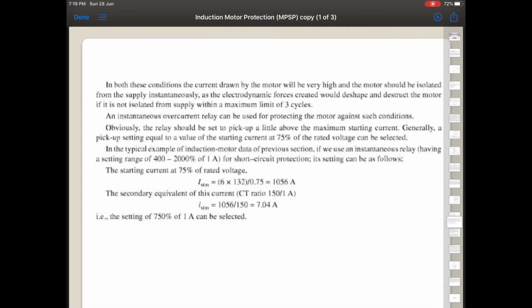and the motor has to be isolated from the power supply, or else, due to this high current under the magnetic field, electrodynamic forces may be caused and it may deform or destroy the motor. This has to be done within 3 cycles of the maximum limit. So if the current has reached a very high magnitude, then within 3 cycles you will have to isolate the motor from the power supply, otherwise it may damage the whole construction of the induction motor.